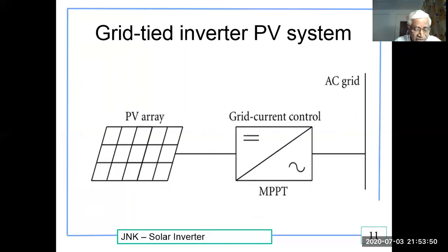The inverter latches onto the grid's frequency and voltage so that the inverter supplies AC power to the grid and acts as a current source, while the role of a constant voltage source in the system is filled by the grid. The grid-connected system topology can only be adopted when there is grid availability in that locality.